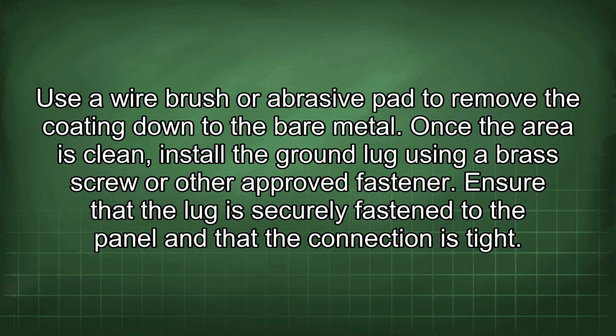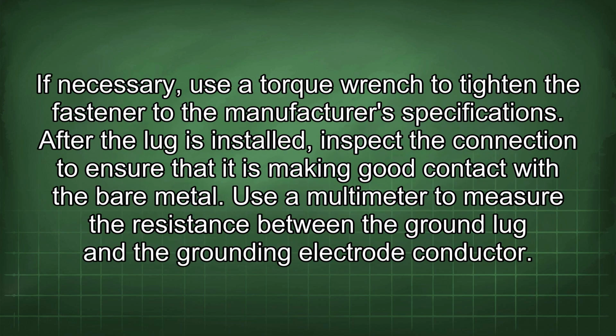Once the area is clean, install the ground lug using a brass screw or other approved fastener. Ensure that the lug is securely fastened to the panel and that the connection is tight. If necessary, use a torque wrench to tighten the fastener to the manufacturer's specifications. After the lug is installed, inspect the connection to ensure that it is making good contact with the bare metal.